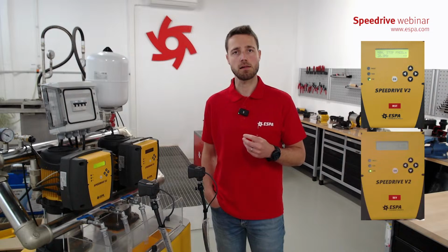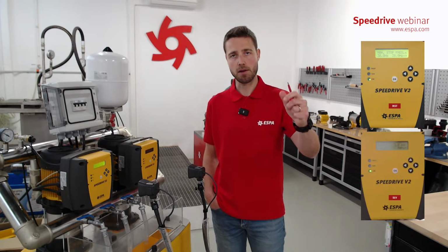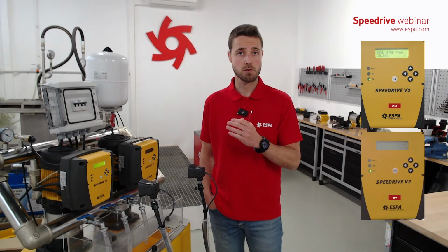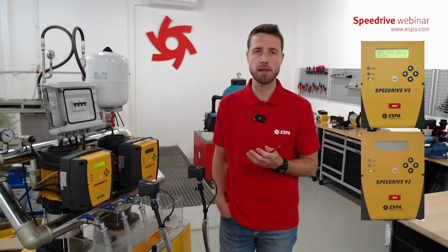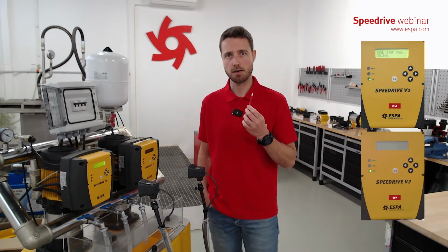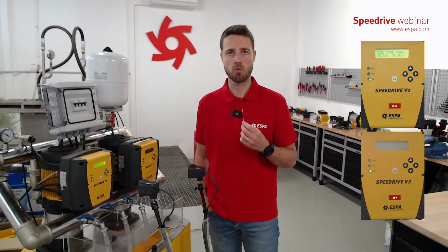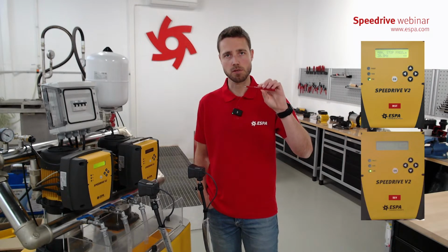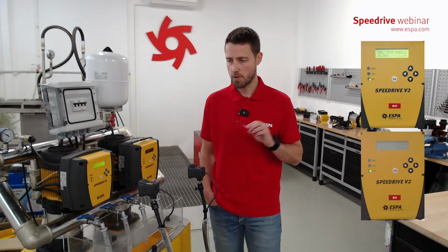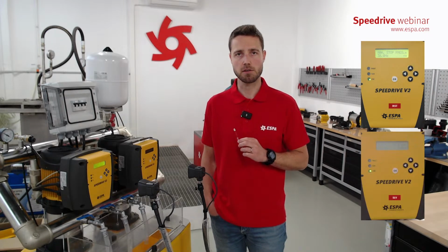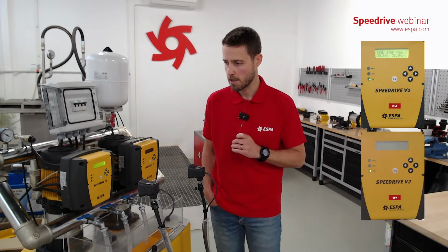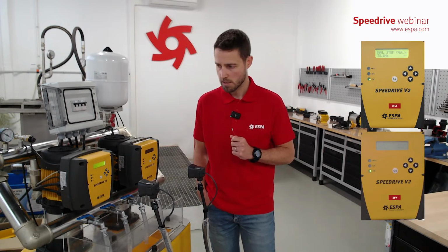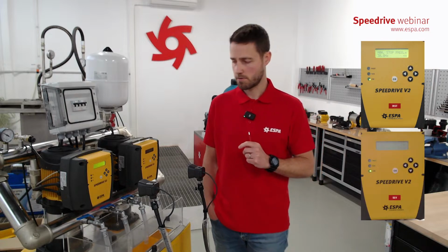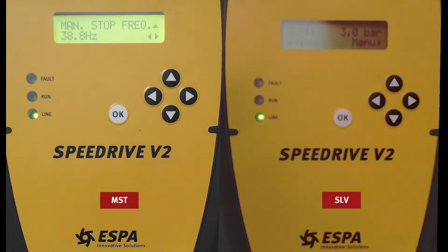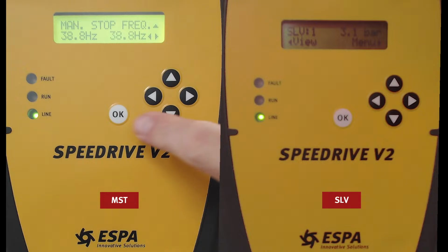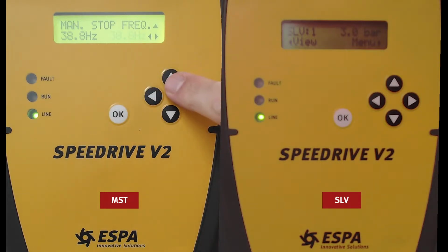If we open all the valves, the pumps are starting, and then we close all the valves and the pumps will not stop, we have to repeat the process and increase 1 Hertz by 1 Hertz. So we have to go up slowly because we cannot add maybe 5 Hertz because then the VFD will stop prematurely. So one by 1 Hertz up. This is the process that I would do or that we recommend. Okay.